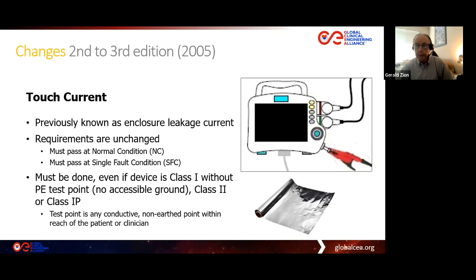So the standards committee's instructions to us are, in these situations, we will use aluminum foil. And typically you use the aluminum foil that you can obtain to wrap your sandwich usually with. You need 2 or 3 thicknesses wrapped together around the edges. And then what you will do is put this in close physical contact with the touchable surfaces of the medical device and tape it down with some kind of tape so that it doesn't shift. And connect your test probe to the aluminum foil.